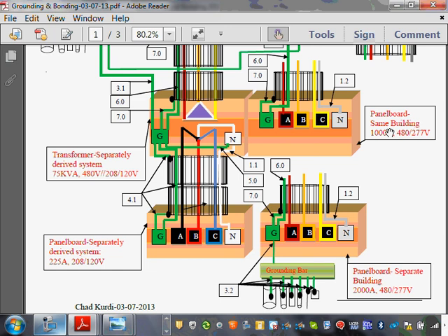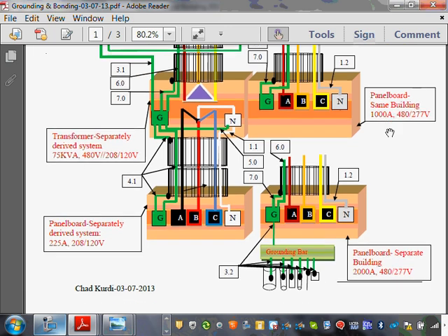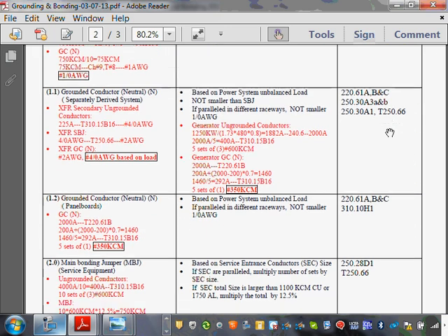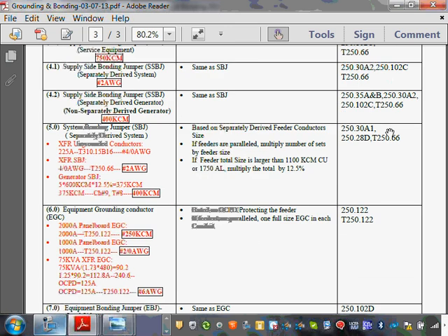Okay, 4.1. How do you size the 4.1? We know it's a supply side bonding jumper now. It's sized exactly as what? Same as the system bonding jumper, and it's number 2. So I hope that by referencing it, you don't have to worry about it. It's exactly like the system bonding jumper all the time. Whatever your system bonding jumper is, the same size is going to be for the supply side bonding jumper. The only time it's different, let me tell you one time when it's different.